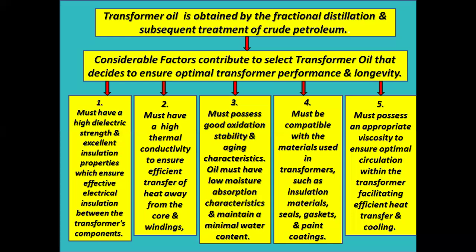Number two, must have a high thermal conductivity to ensure efficient transfer of heat away from the core and windings. Number three, must possess good oxidation stability and aging characteristics. Oil must have low moisture absorption characteristics and maintain a minimal water content.